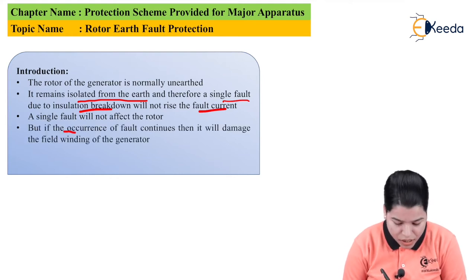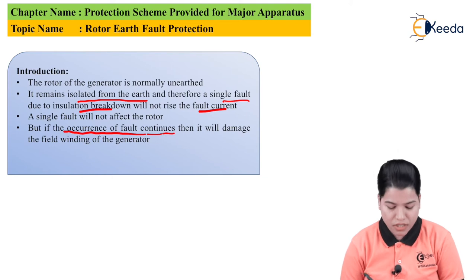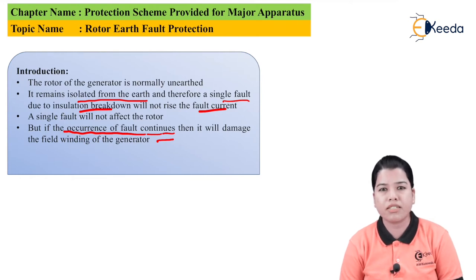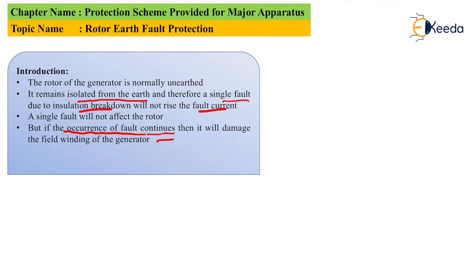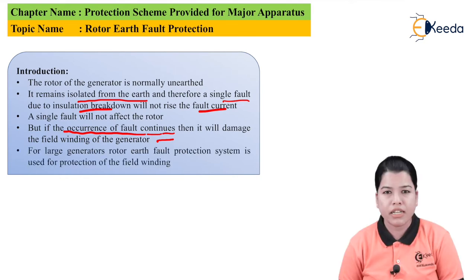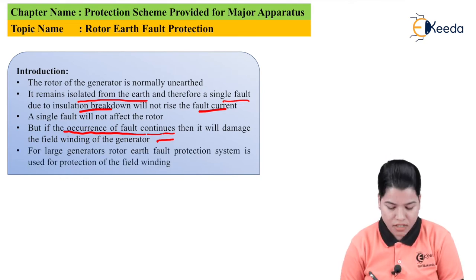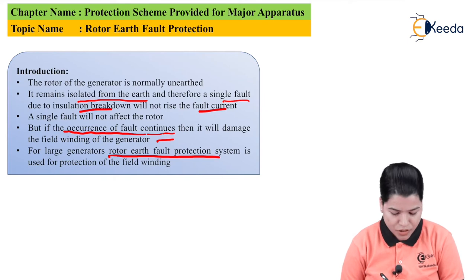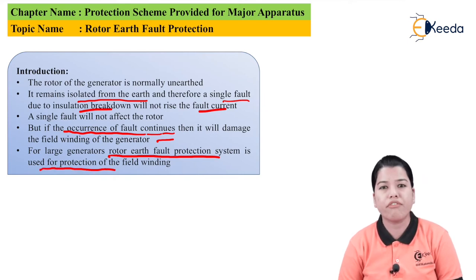But if the occurrence of the fault continues, it will damage the field winding of the generator. One fault will not affect the rotor, but if the fault persists — that is, if the fault occurs again and again — then the field winding of the generator will get damaged. Therefore, for large generators, a rotor earth fault protection system is used for the protection of the field winding.